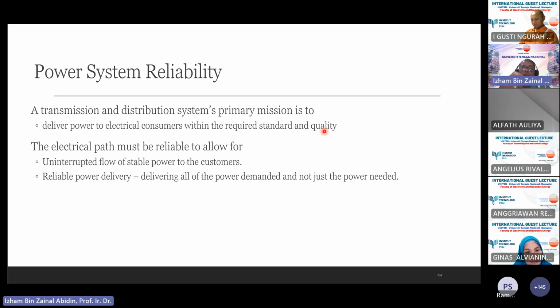So that's why you cannot put industries which use sensitive equipment, say for example, semiconductor companies, beside a metal smelting plant. You cannot do that because a metal smelting plant will create a lot of harmonics to the distribution network and will cause problems to the semiconductor plant. So that's why you notice in the place where I have semiconductor plants, it is all the same type of plants nearby. Big industries are all nearby, so that I can control the harmonic flow in the distribution network. Regardless, everything is to ensure that it must be uninterrupted and it must be reliable.